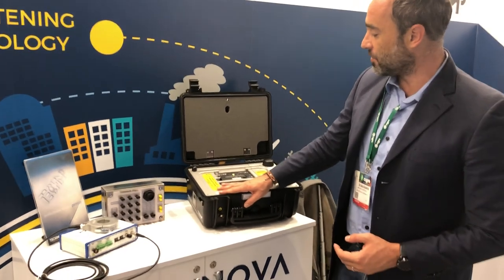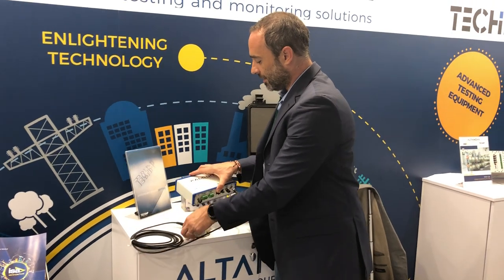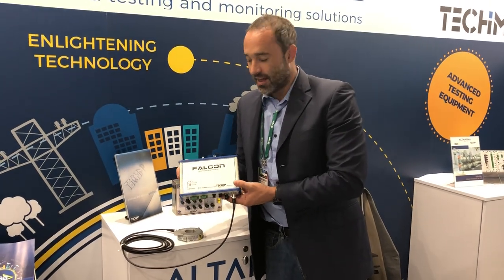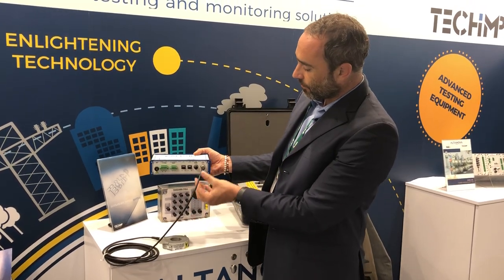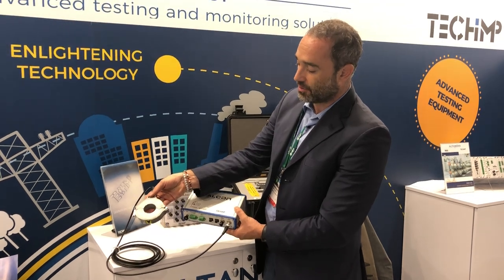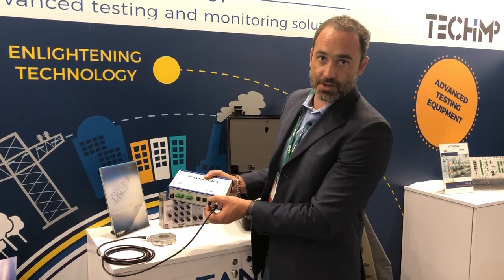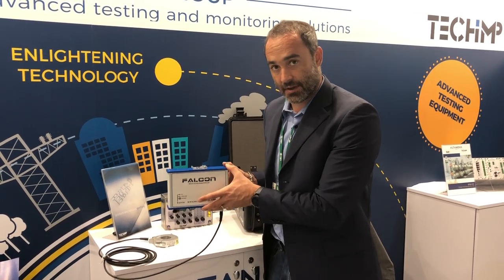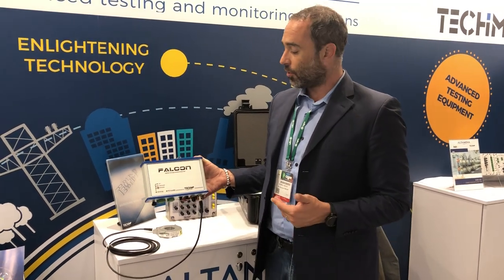Apart from the Aquila acquisition unit for spot testing, the latest product from TECHIMP is the Falcon. The Falcon is a device for medium voltage monitoring. It uses one PD input — in this case an HFCT — one input for synchronization, and two inputs for communication via Ethernet. This low-cost device can be used to test medium voltage cables, motors, switchgear, and similar assets.